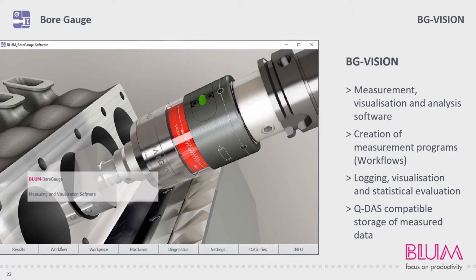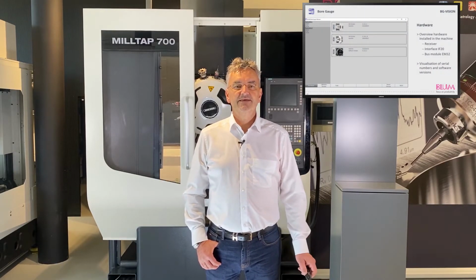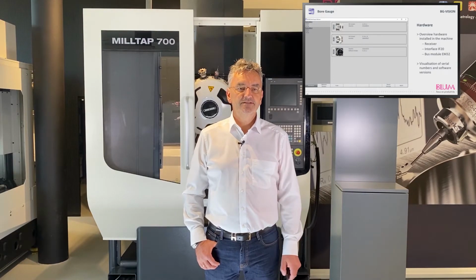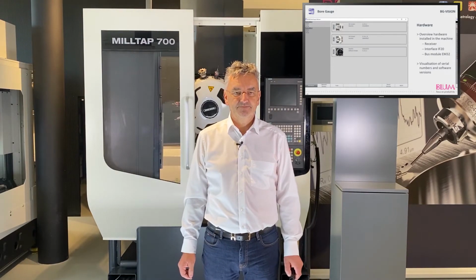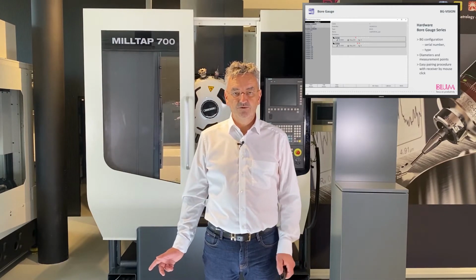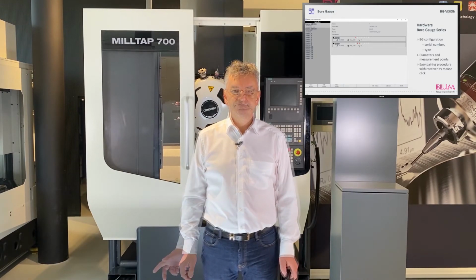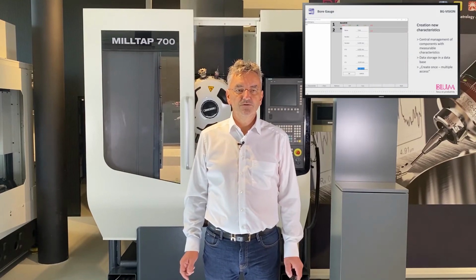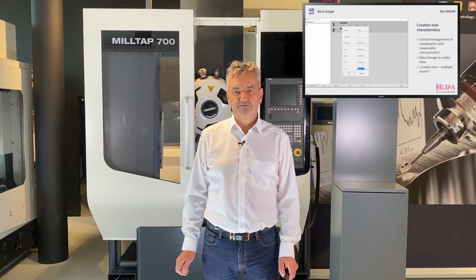The program can be used to create so-called workflows, for example sequence programs for a measuring process. Further, it's also applied to log and visualize measured values and an associated statistical evaluation. The program supplies Q-DAS-compatible data. When used for diagnostic purposes, BG Vision provides a quick overview of the hardware components installed on the machine. In addition, the data from all the installed bore gauges is stored in the program, including the actual diameters and corresponding measuring points.